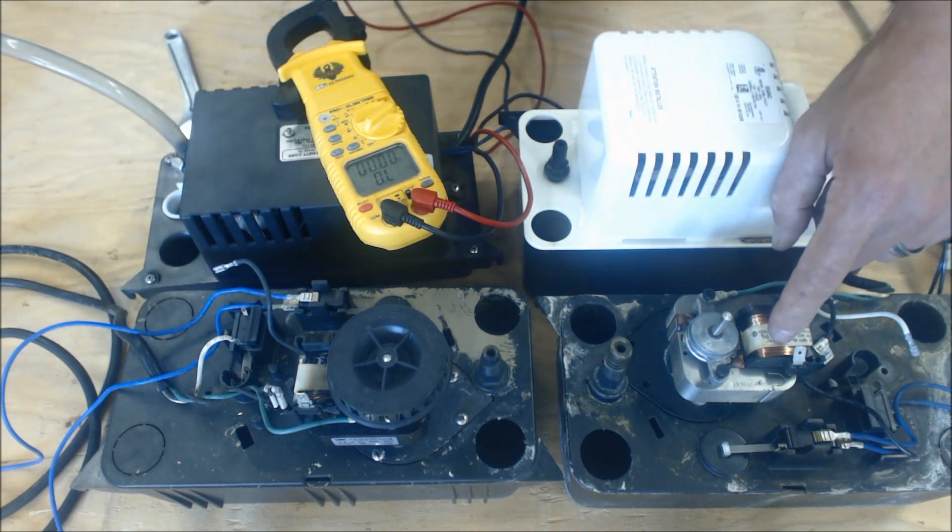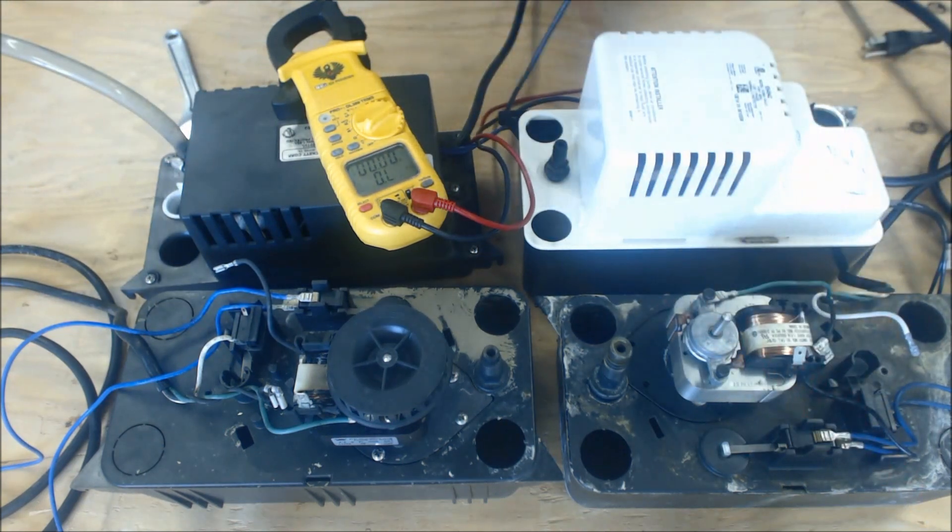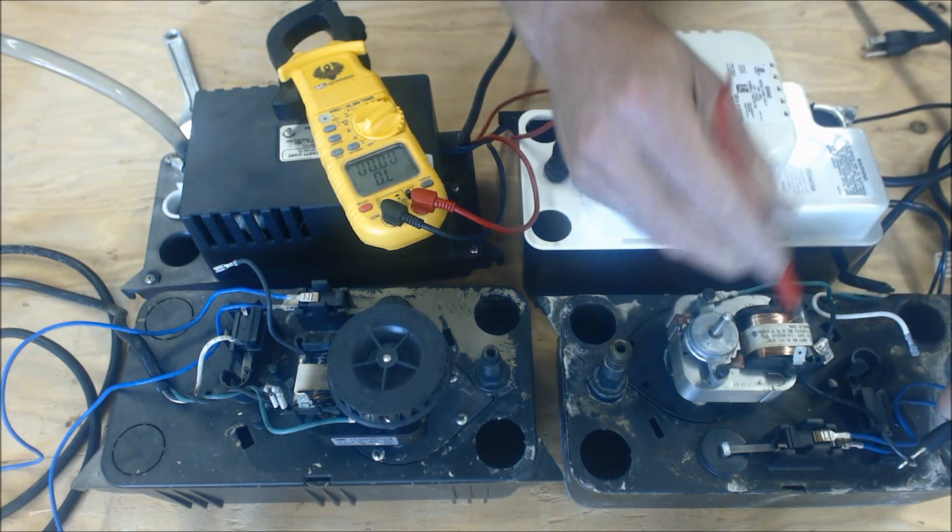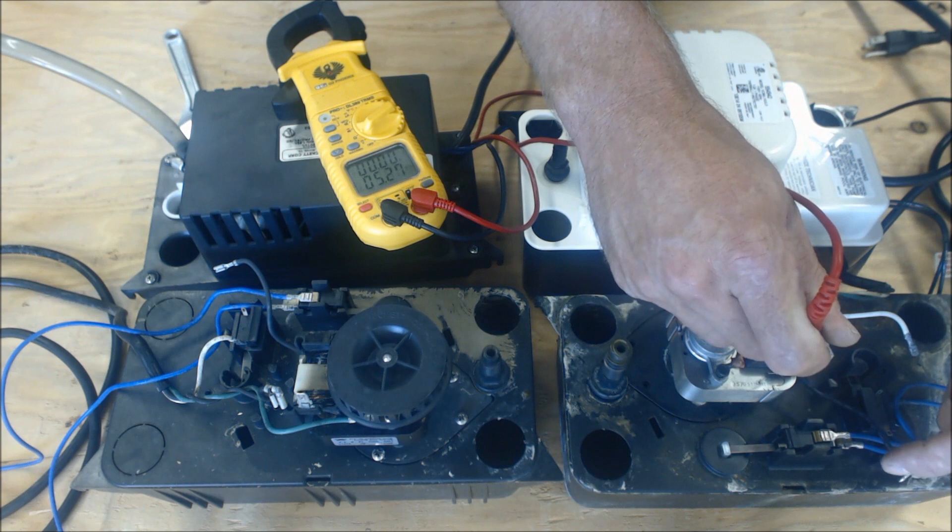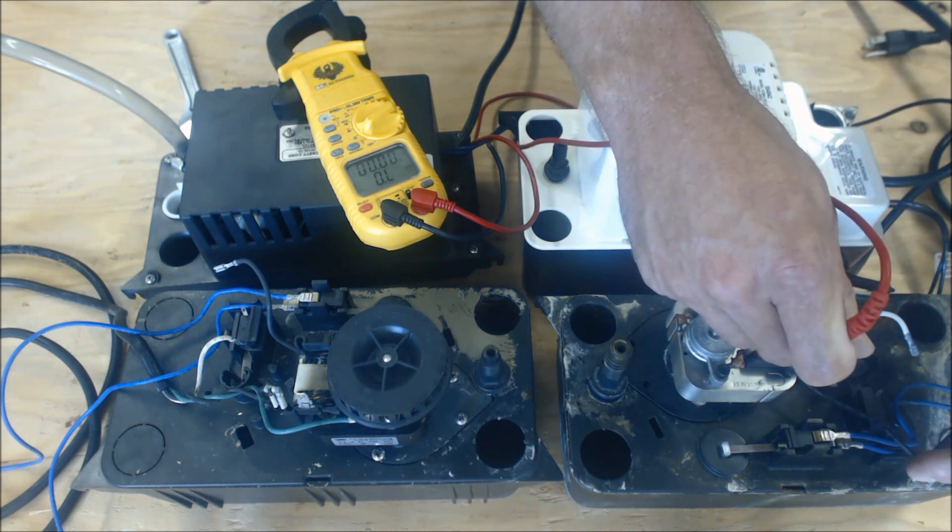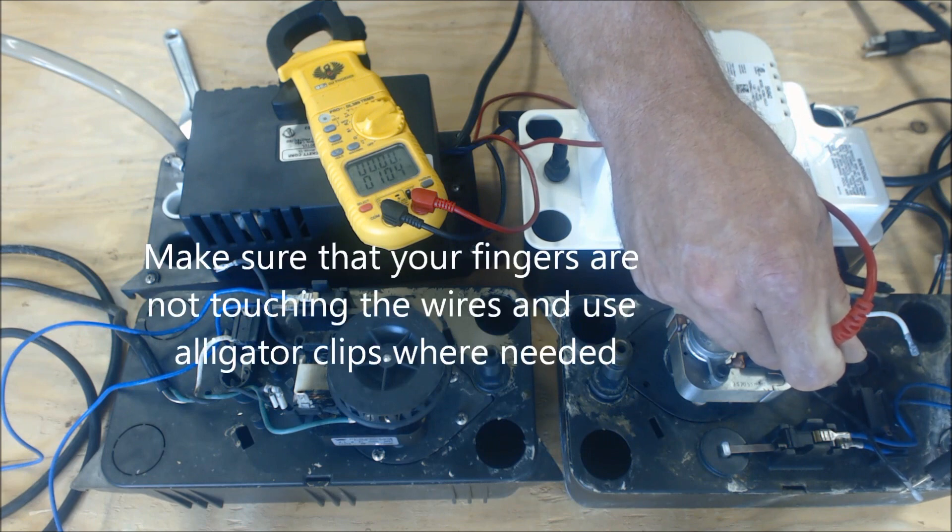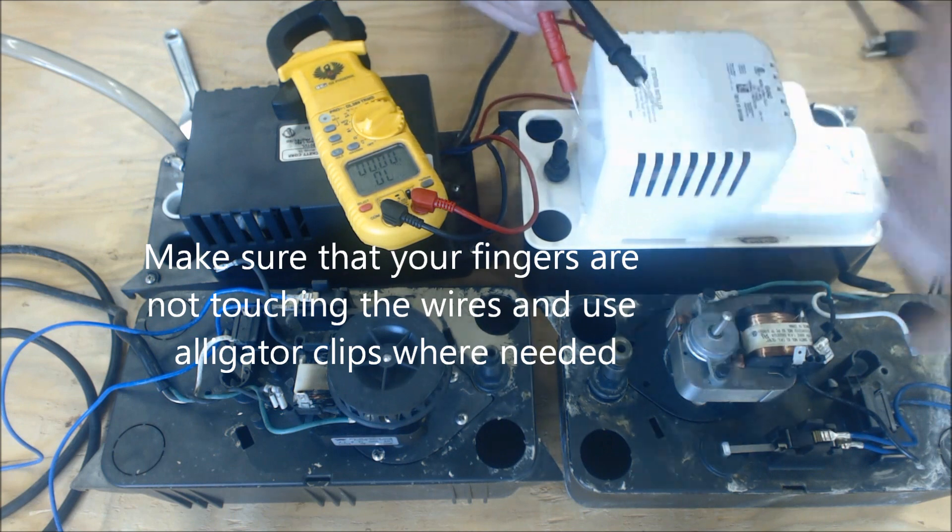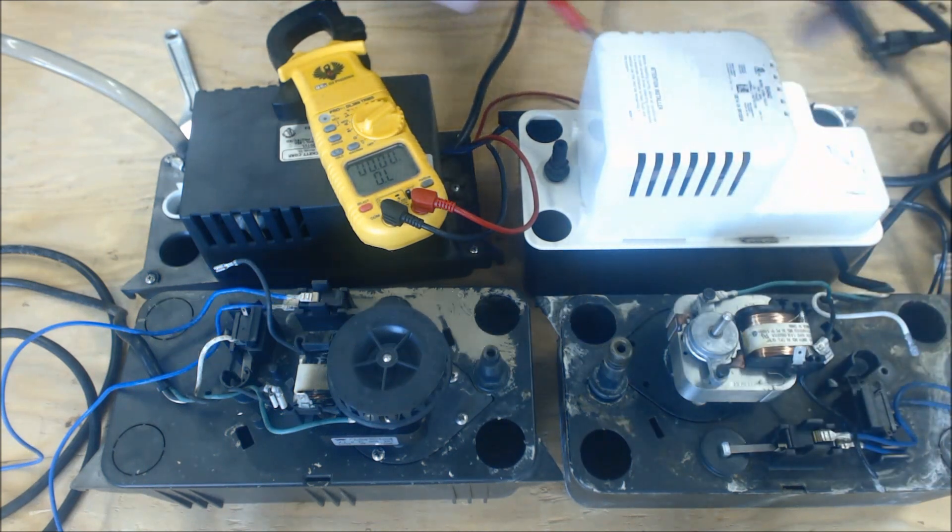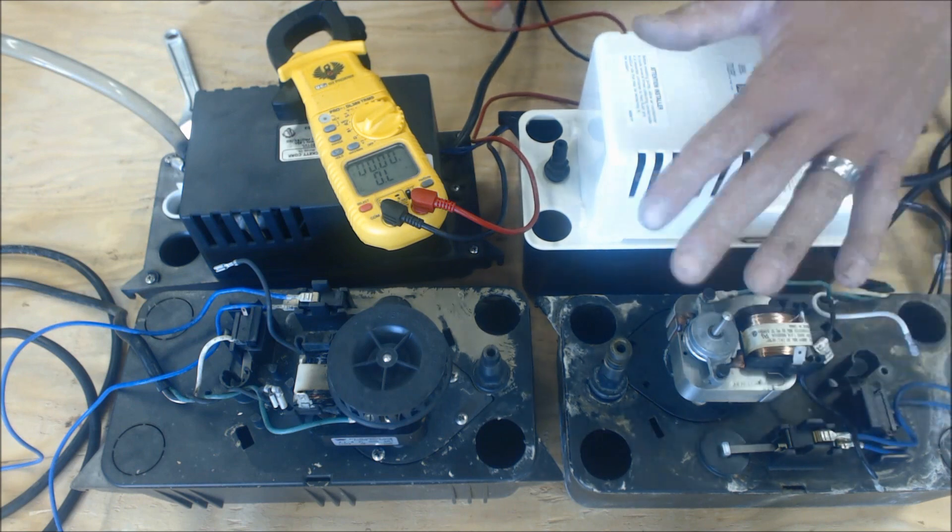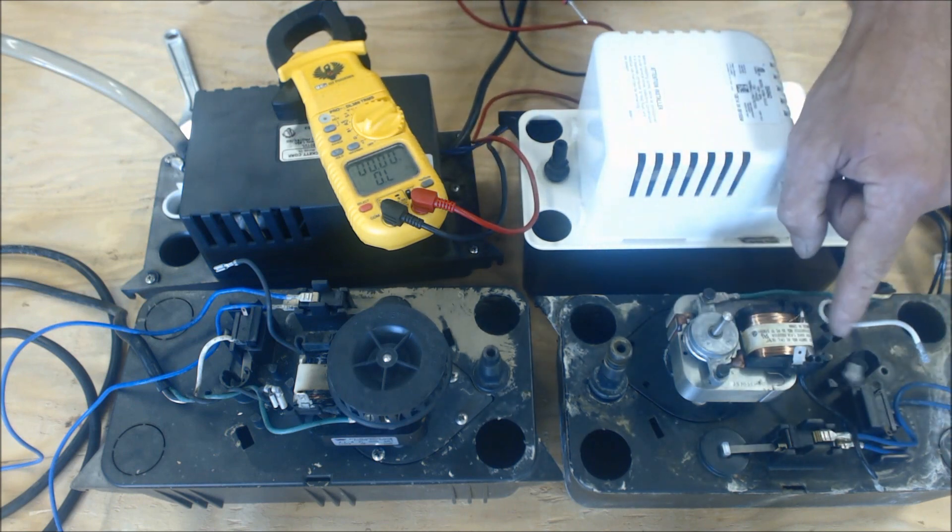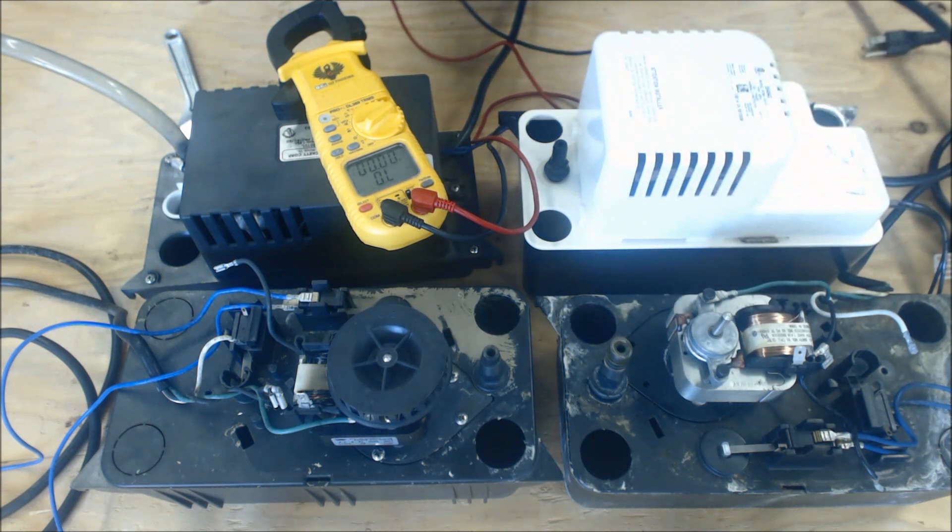Versus this motor right here, this motor is actually in okay shape. And that one we have 10 ohms of resistance. If you have alligator clips, you can just alligator clip it onto the wire, that makes a good connection. So you have 10 ohms of resistance. Normally you're looking anywhere from about 10 to 16 ohms of resistance on these condensate pumps.